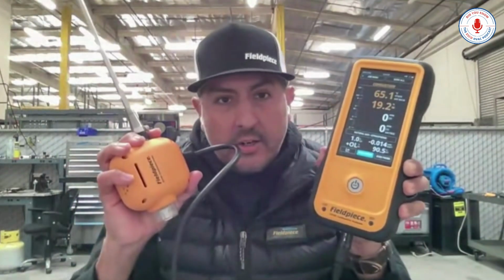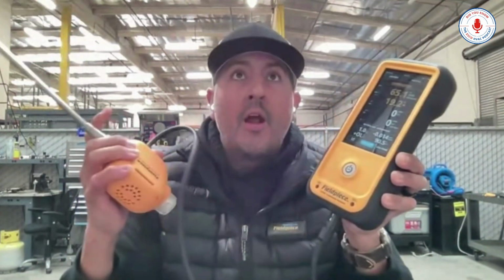What's less known is that in your typical combustion analyzer you have two primary sensors: an oxygen sensor and a carbon monoxide sensor. What a contractor may not know is that by simple exposure to ambient air, those sensors are degrading over time, whether the tool is being used or not. So typically a contractor needs to swap out a sensor every one or two years, depending on the activity of the tool.